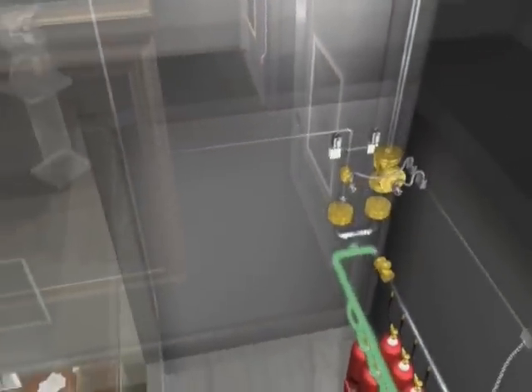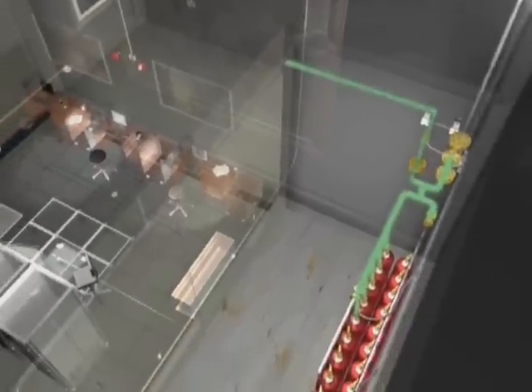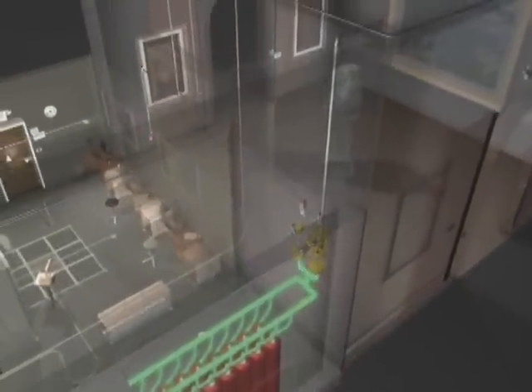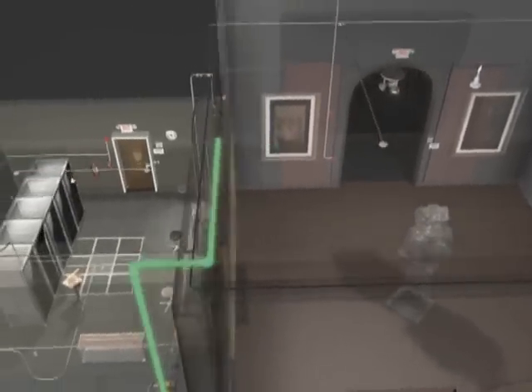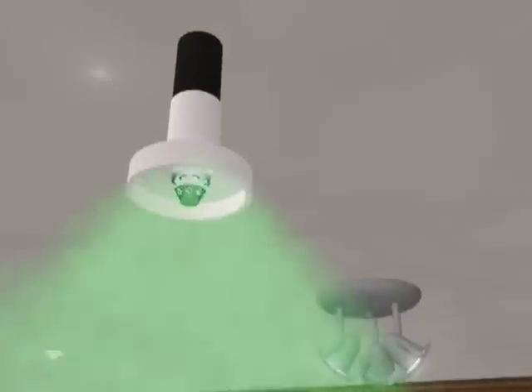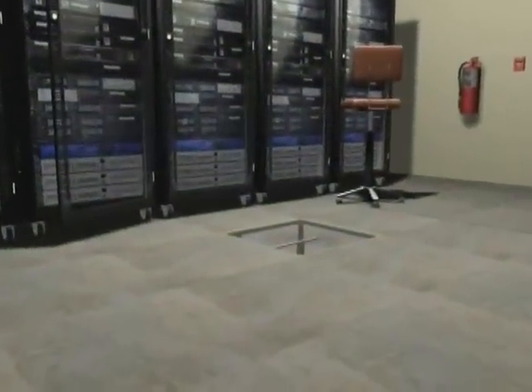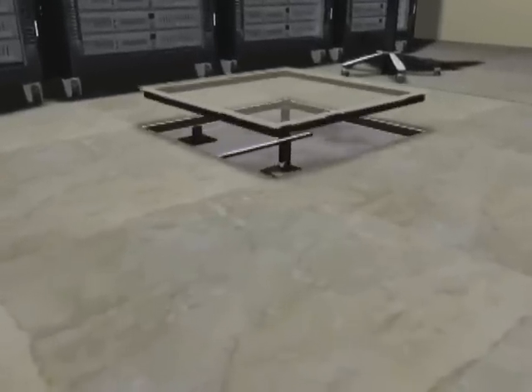The Inergen agent is then distributed throughout the piping network. In overhead installations, nozzles are fitted with a deflector shield to direct the agent flow into the hazard. These specifically designed nozzles quickly discharge Inergen into the protected zone.